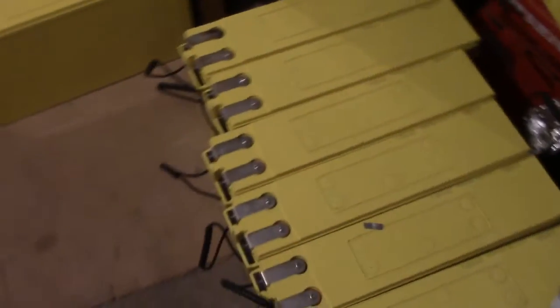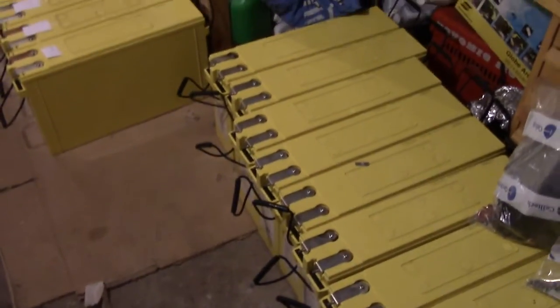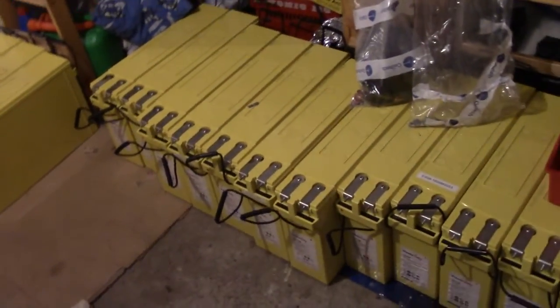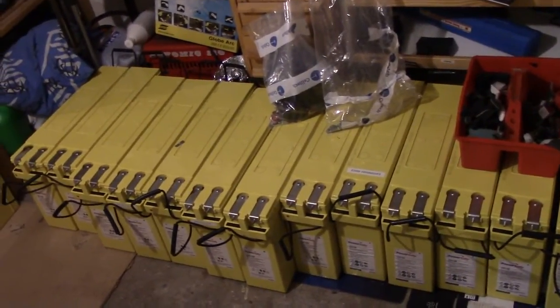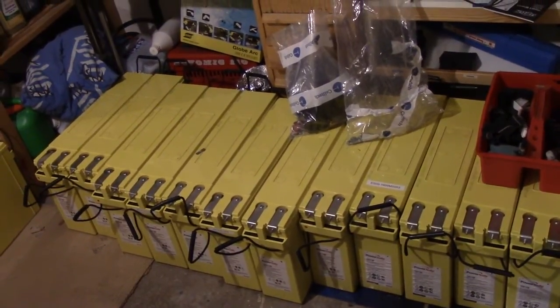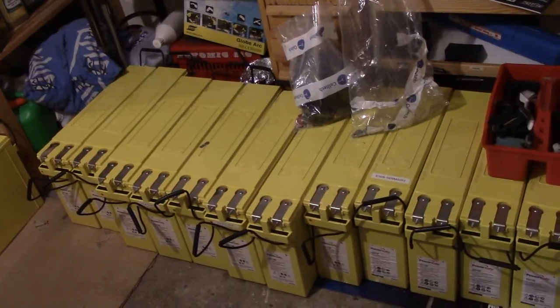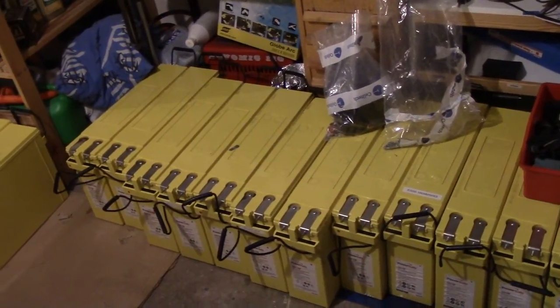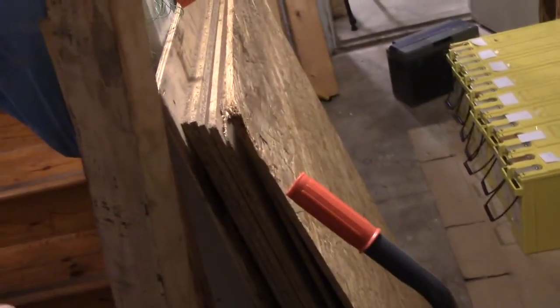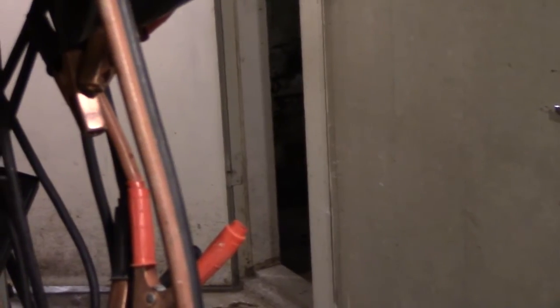I've measured the voltage on them and although they're taken out of duty today so their voltages are going to be rather high, they were all within very tight tolerances, all of them within 13.15 to 13.23 volts or something like that. So now I'm going to clean those terminals up, then get to work on constructing some racks, then after the outside dries up I'm going to take care of the leak in the battery room, and then hopefully install the batteries along with my fancy new technology which is arriving shortly.